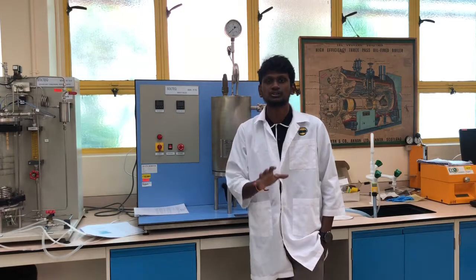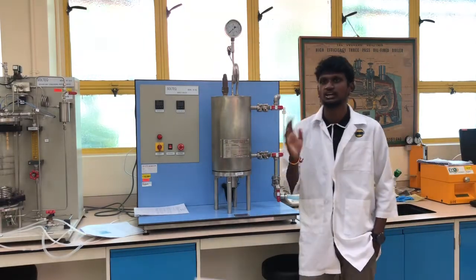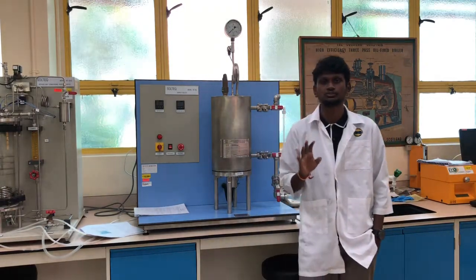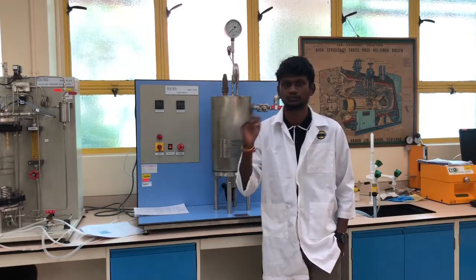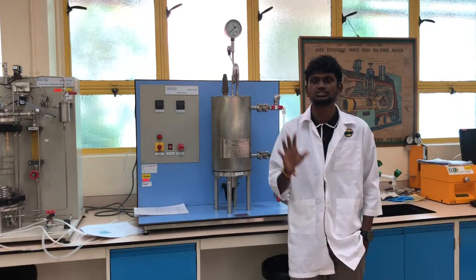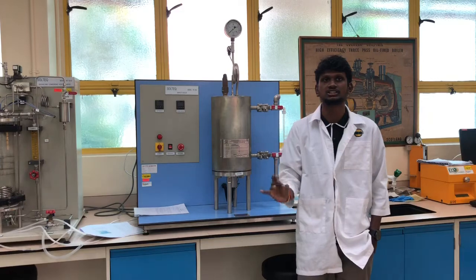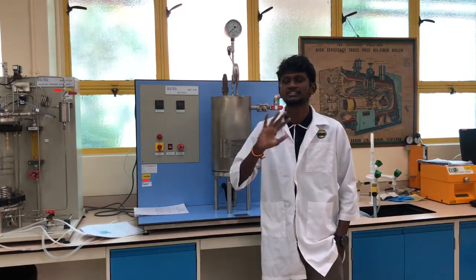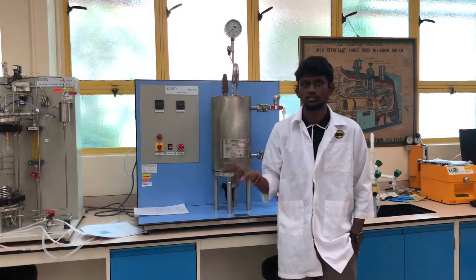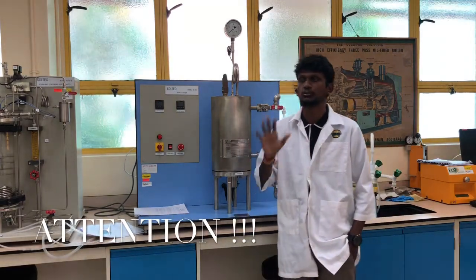Now, the precautions when handling this boiler. There are four main precautions when handling this Marcet Boiler. The first one is to always check for leakage of air, water, or steam at any suspicious place. The second one is to make sure that all the parts are insulated and do not touch them with your bare hands because it is extremely hot.